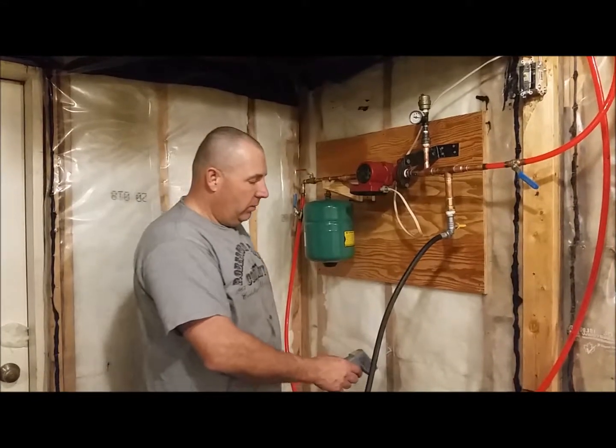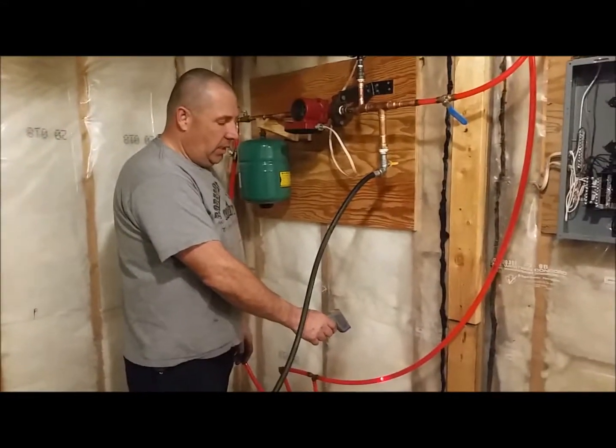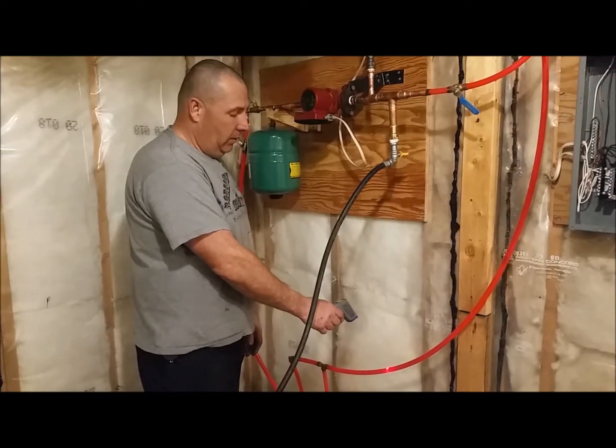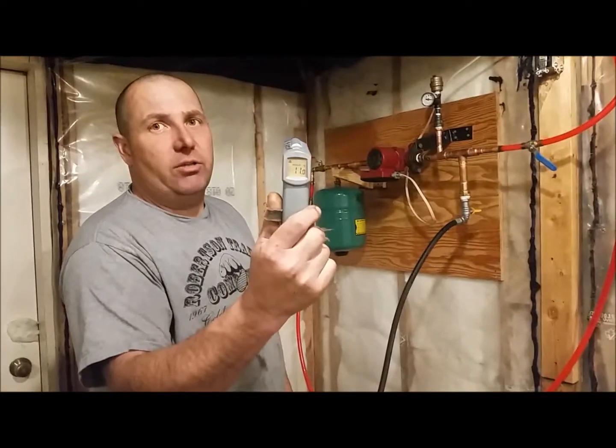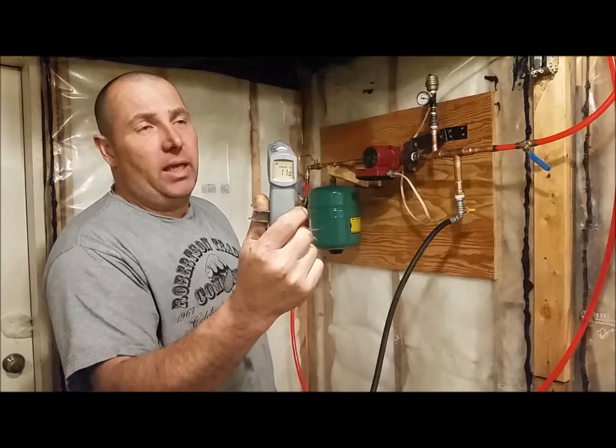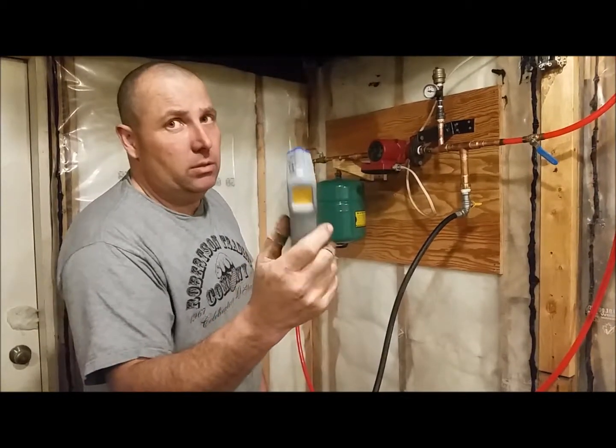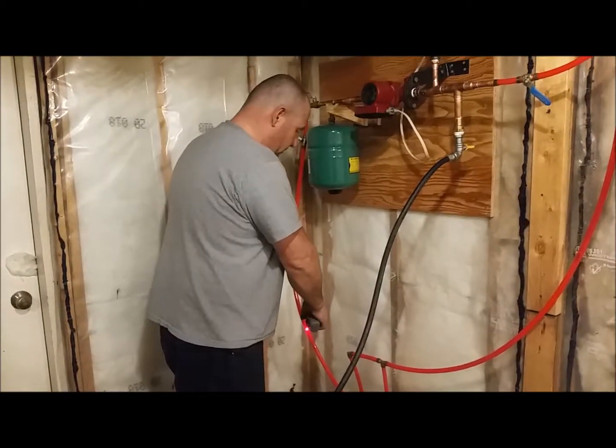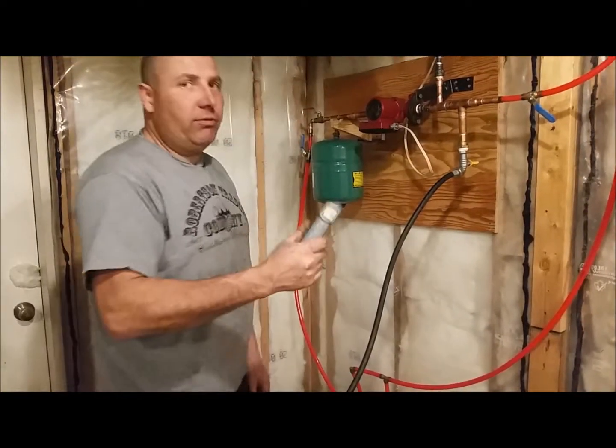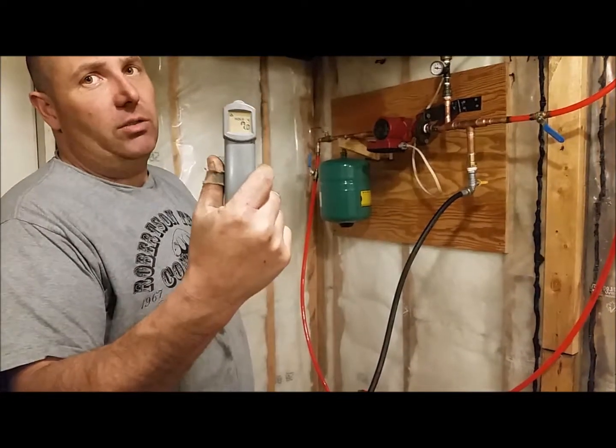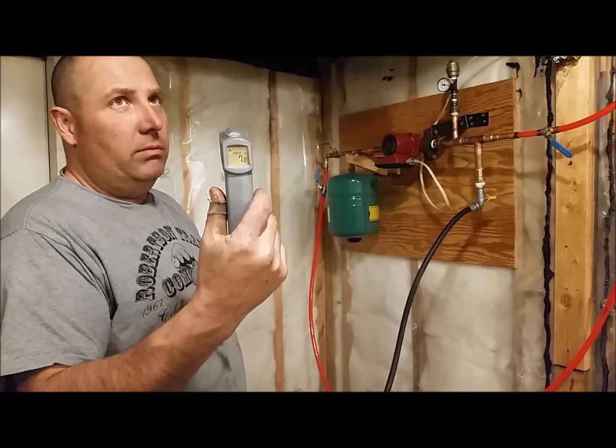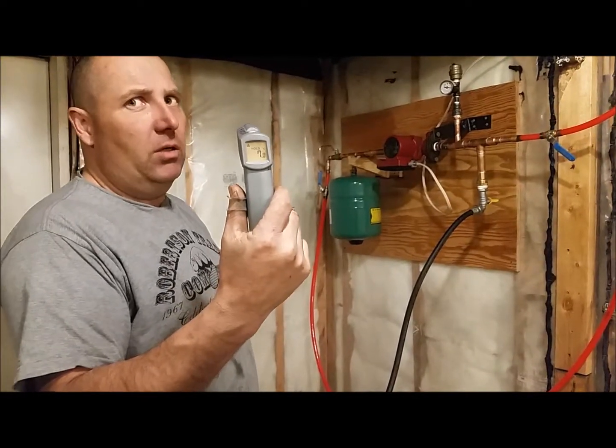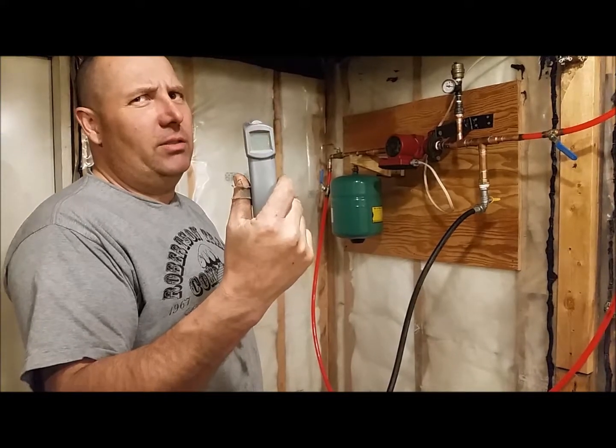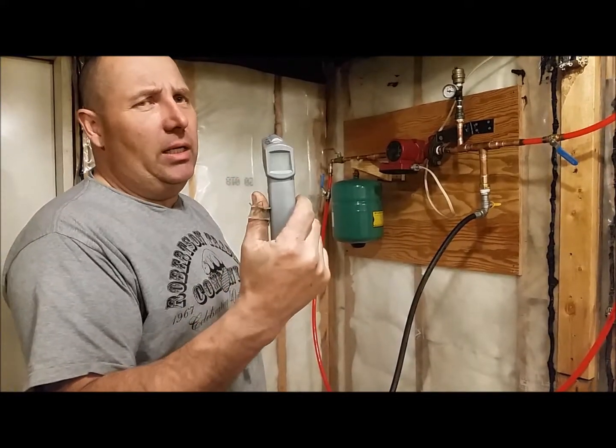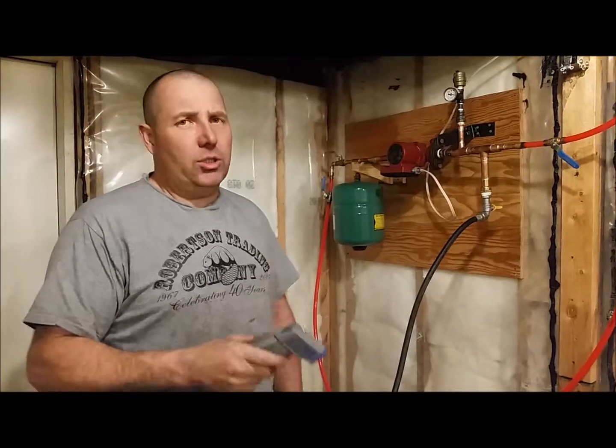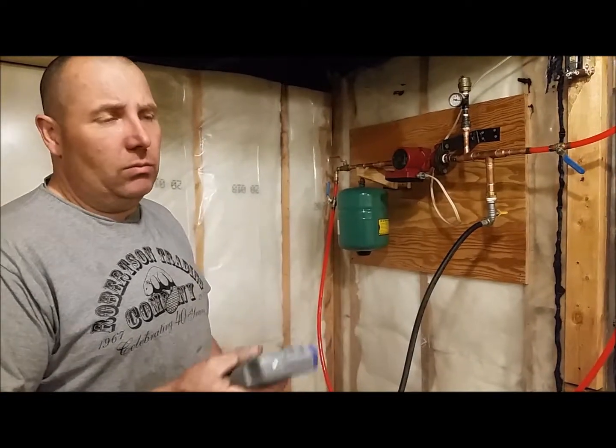All right, so we're going to start. We'll take a temperature of the heat exchanger supply line right here. It is 11 degrees Celsius getting to the floor from the heat exchanger. Coming out of the floor is 7 degrees. So we have about a 4 degree, where's my math? 11, that's a 4 degree heat differential right now. So the floor is absorbing heat is basically what comes of that.